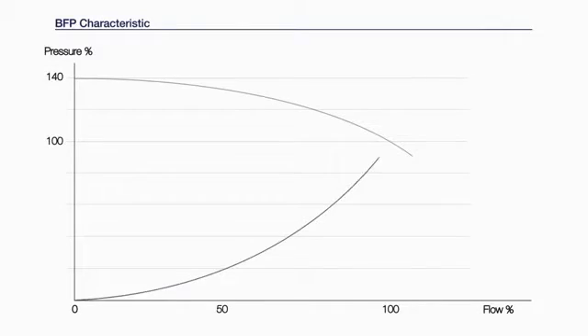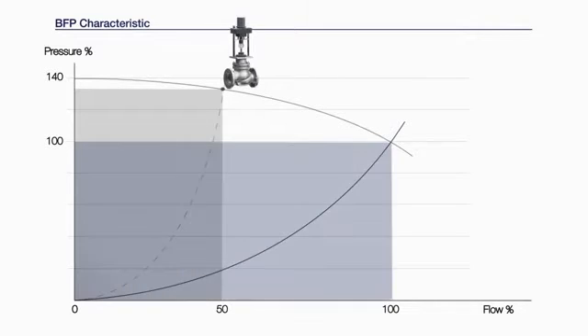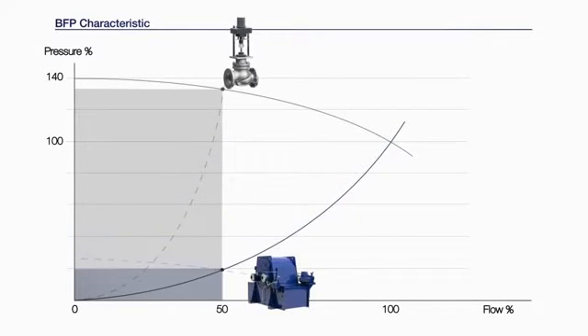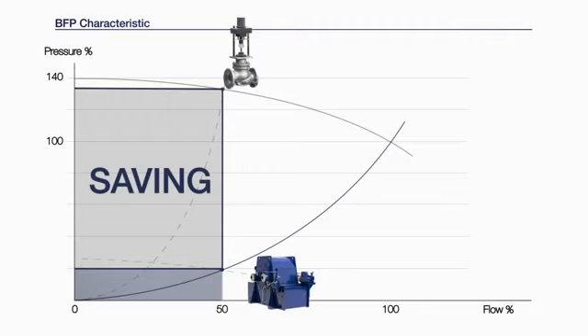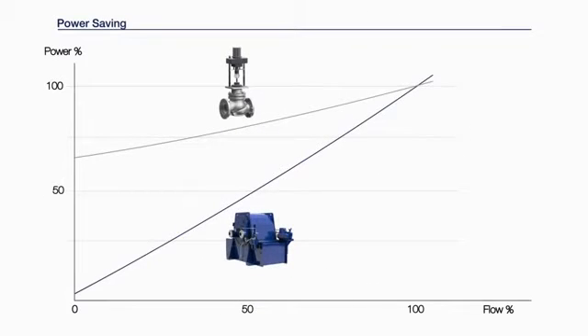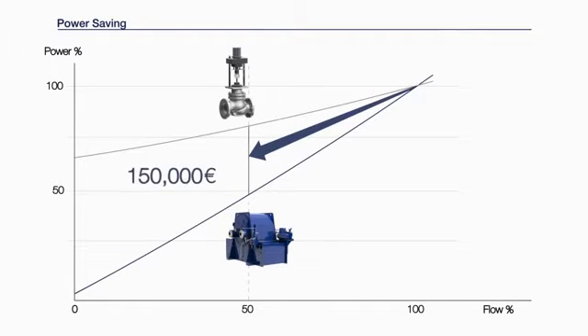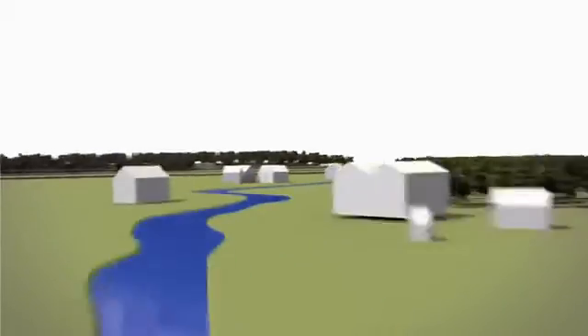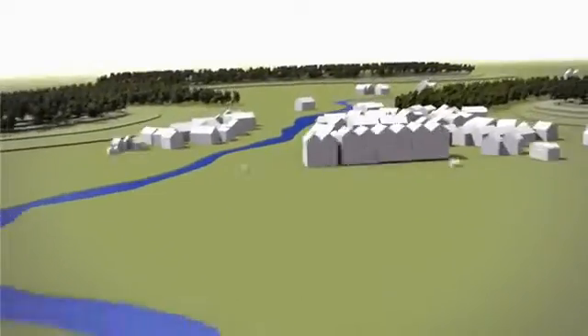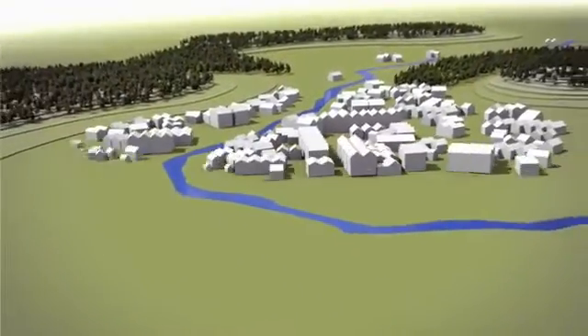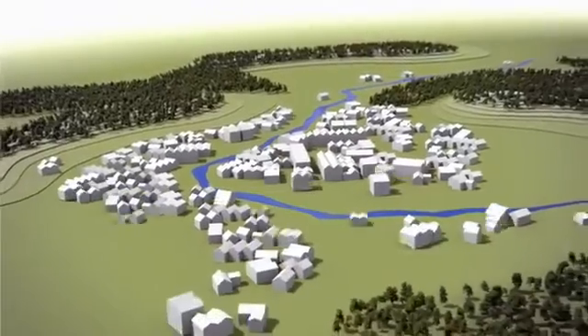Using variable speed coupling also yields tremendous energy savings. Energy savings of up to 2.5 million kilowatt hours per year can be achieved even in baseload power plants with a 420 megawatt block output. That's enough energy to supply 600 homes with power for a year. Under partial load operations, the savings are even greater.